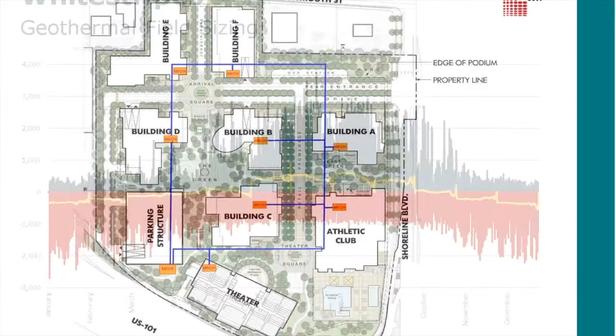Here's a calculation we did for the load on the buildings, and with heat recovery from geothermal, the orange line is the load you really need to meet. We could get 1,500 tons out of a slinky filling that whole site, which is great news — it takes care of the cooling peak for about 80% of all the hours in the year. But to really achieve that peak, geothermal gets expensive, because we'd have to do vertical bores, and that's another 10 million just for those.